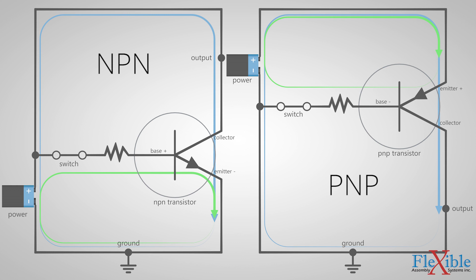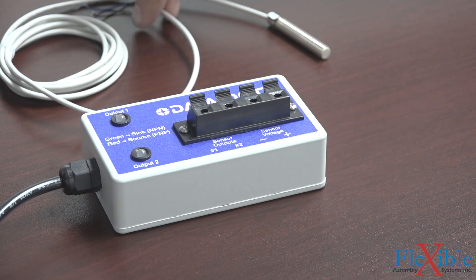That is why PNP sensors are called sourcing sensors, since they source positive power to the output. And NPN sensors are called sinking sensors, since they sink ground to the output. That makes these transistors complementary.